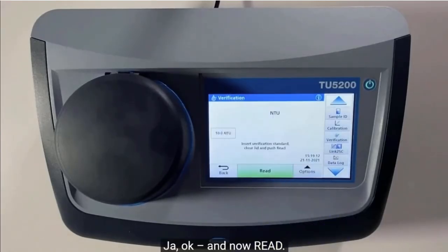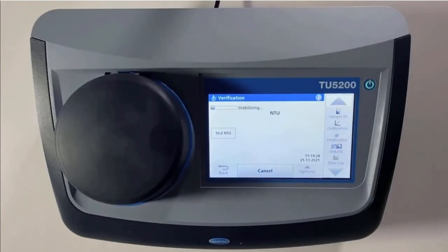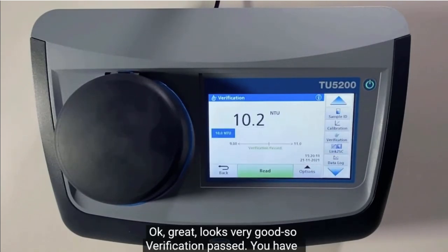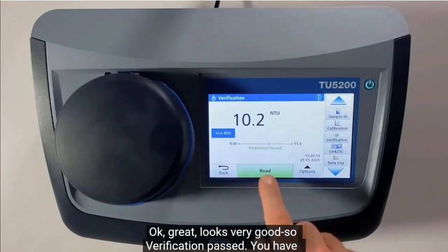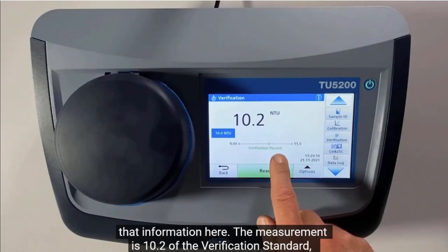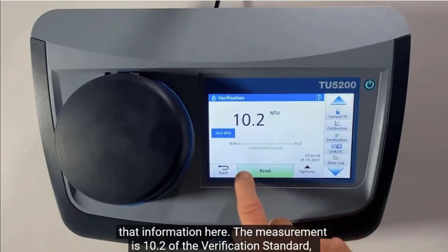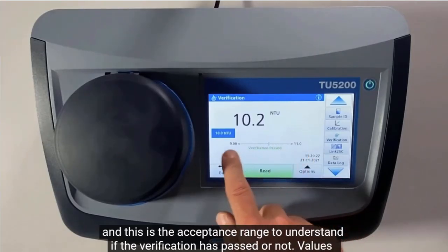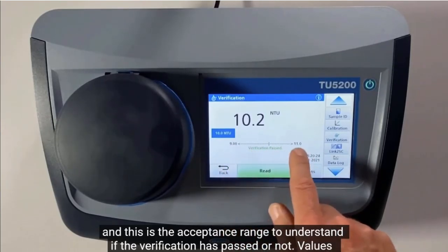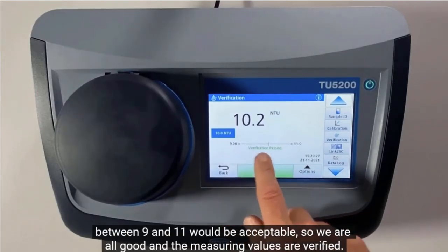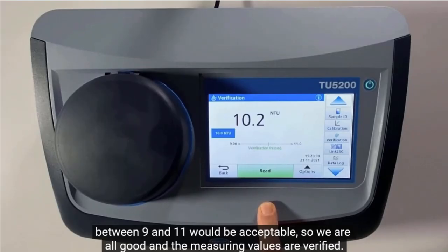Yeah, okay. And now read. Okay, great, looks very good. So verification passed, you have that information here. So the measurement is 10.2 of the verification standard, and this is the acceptance range to understand if the verification has passed or not. So values between 9 and 11 would be acceptable, and so we are all good. So the measuring values are verified. Thank you very much.